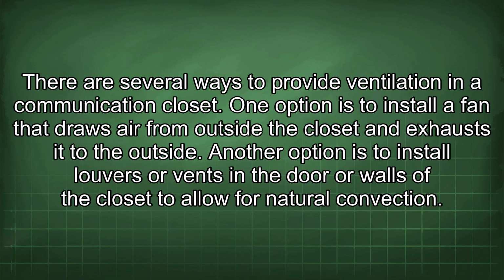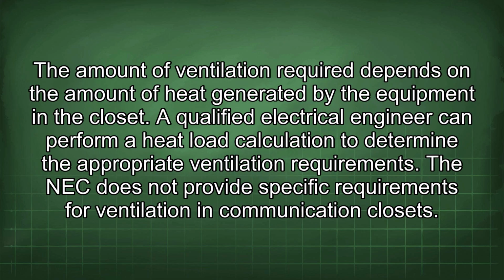There are several ways to provide ventilation in a communication closet. One option is to install a fan that draws air from outside the closet and exhausts it to the outside. Another option is to install louvers or vents in the door or walls of the closet to allow for natural convection. The amount of ventilation required depends on the amount of heat generated by the equipment in the closet. A qualified electrical engineer can perform a heat load calculation to determine the appropriate ventilation requirements.